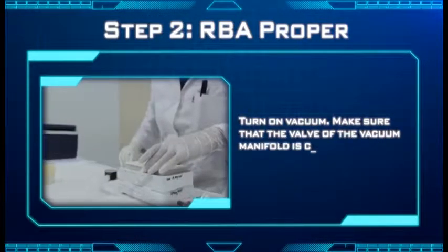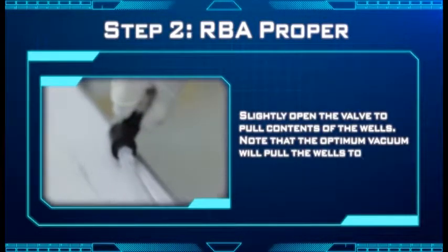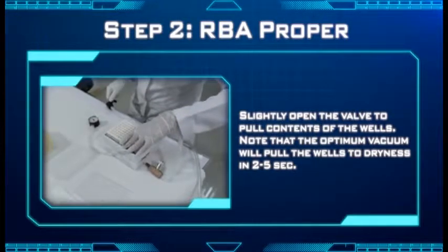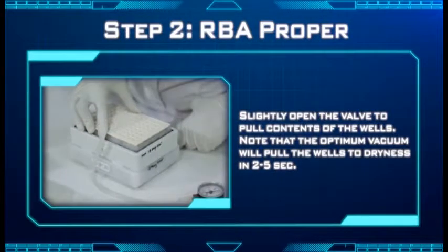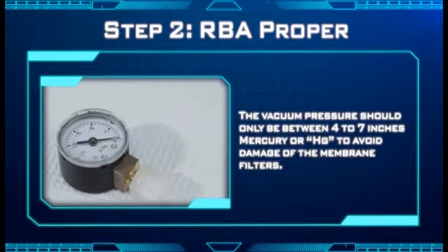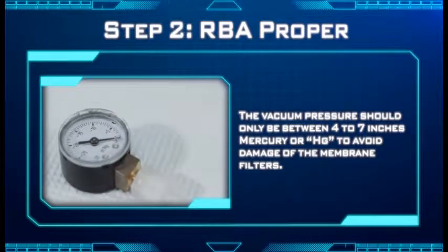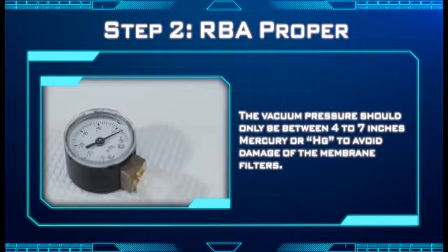Turn on vacuum. Make sure that the valve of the vacuum manifold is closed. Slightly open the valve to pull contents of the wells. Note that the optimum vacuum will pull the wells to dryness in 2 to 5 seconds.